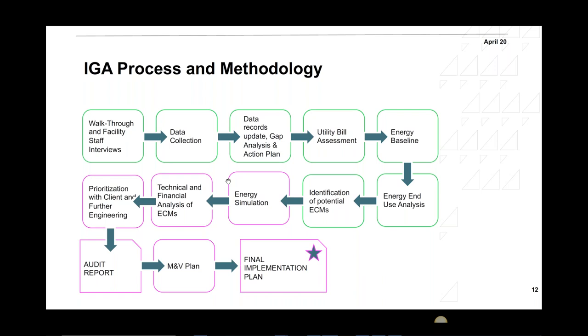Then normally, if it's an ESCO project, you'd go with an M&V plan. So what is the measurement and verification plan? How are we going to verify the savings? We're going to say, I'm going to save this much by changing the chiller. How do I measure and verify that these savings have occurred? So there would be an M&V plan. We're not going to talk about that. Maybe we can have another webinar on that. And then you go with the final implementation plan to show when everything will happen on site and offsite as well, and that will be submitted to the client for their approval.